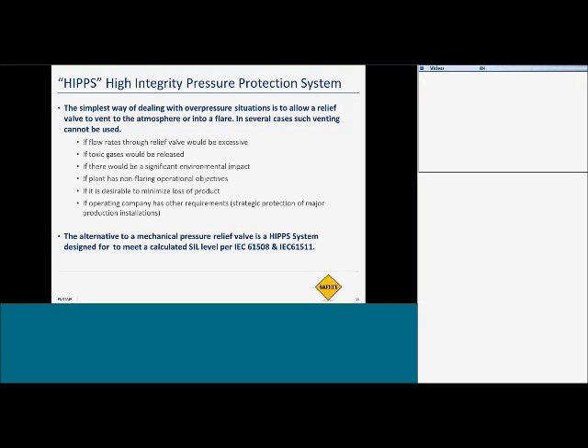If toxic gases could be released, they may want a HIPPS system. If there could be significant environmental impact or potentially fines, for example, if they have a flaring capacity that could be exceeded with a discharge, then there's big issues with that. So they may need a HIPPS system. If they want to minimize the loss of their product, they don't want to flare off a lot of that product and lose it, they may install a HIPPS system. So these are some of the most common reasons that customers install HIPPS.